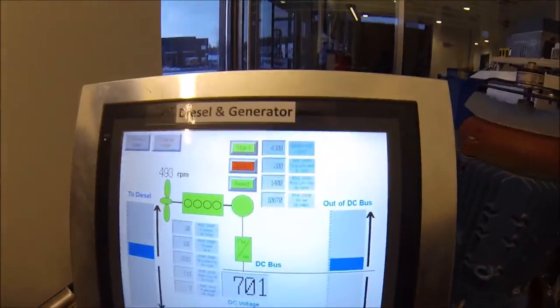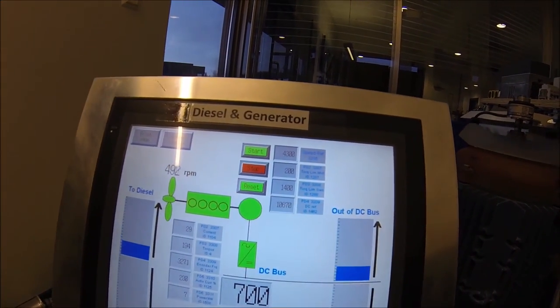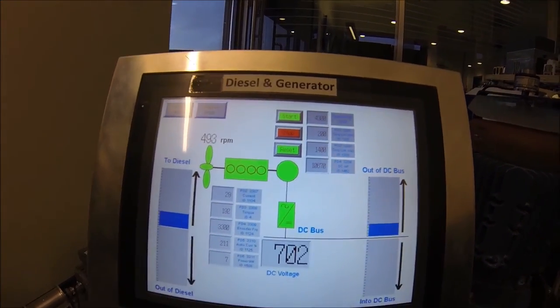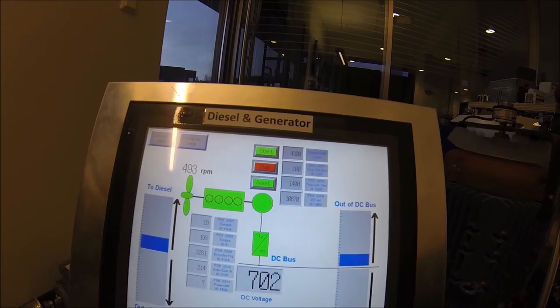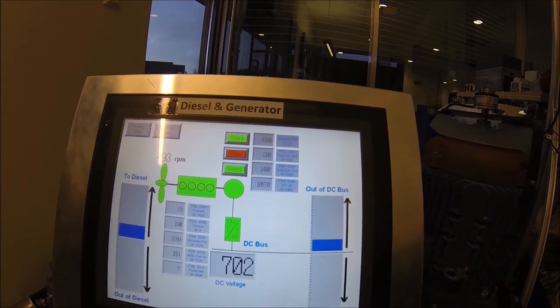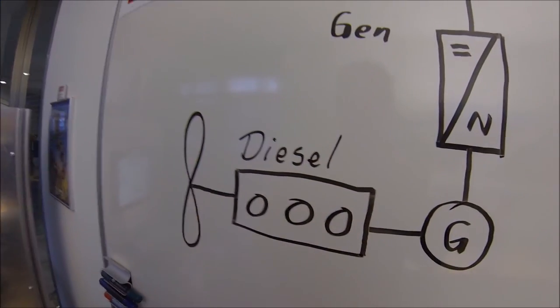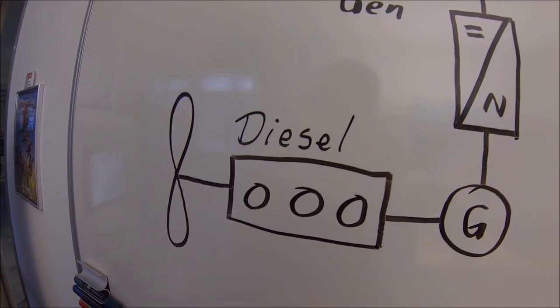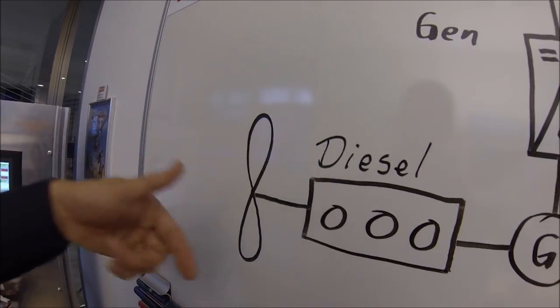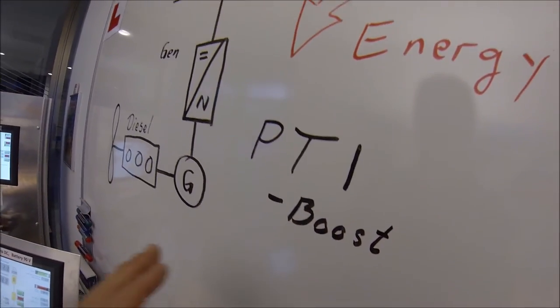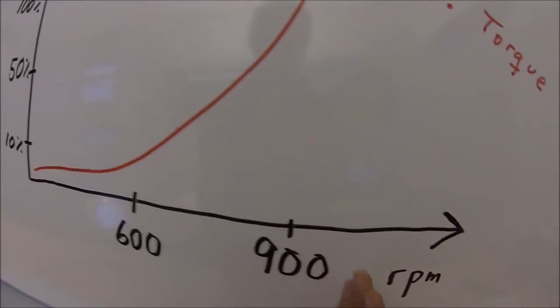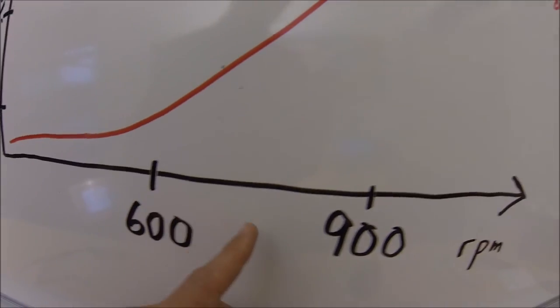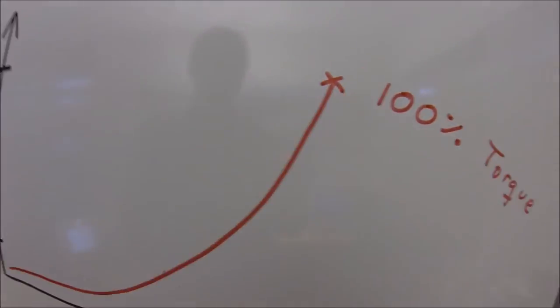What is the difference between PTI zero speed and PTI boost mode? The boost mode is more for running against a torque reference, while PTI zero speed is more for speed reference with a torque limit. When boosting a diesel engine it is important to not boost too much — the diesel engine only wants a positive load from the process. We can ensure this with a torque limit given from the power management system, or we put into the drive a curve which defines the maximum amount of torque allowed as a function of RPM, ensuring the torque is not ramped up before the diesel is in its optimal RPM range.